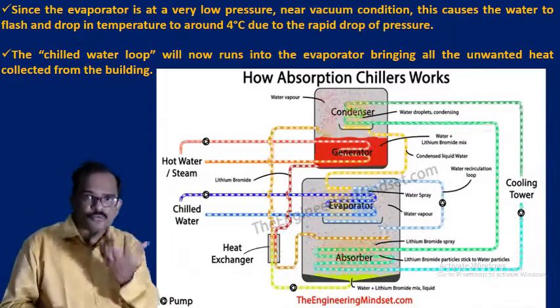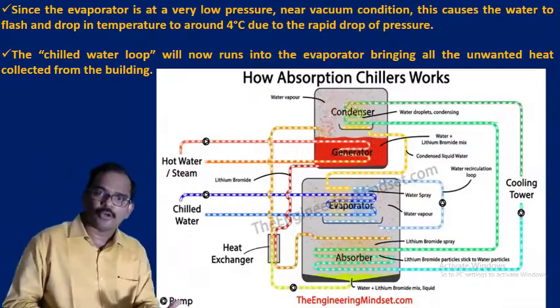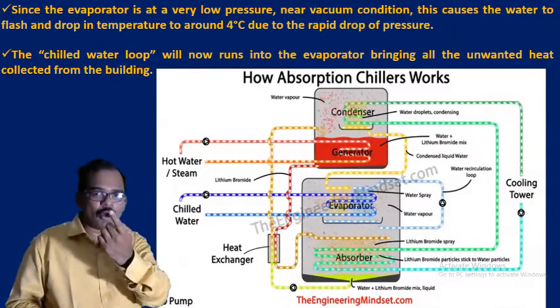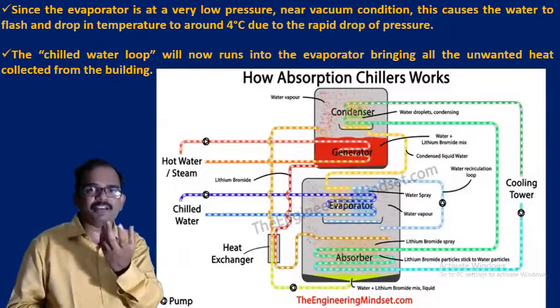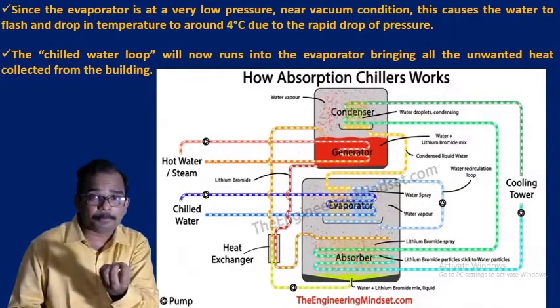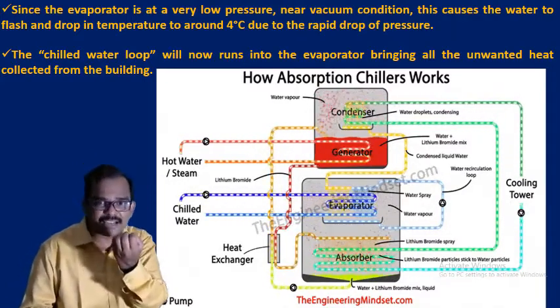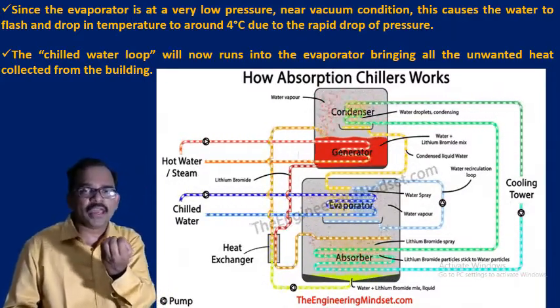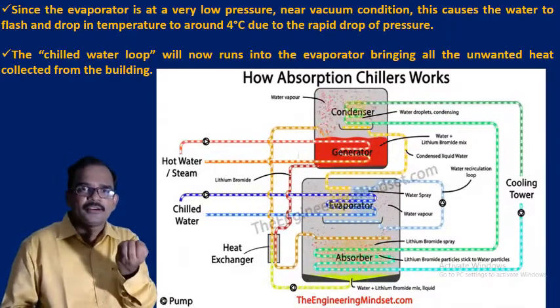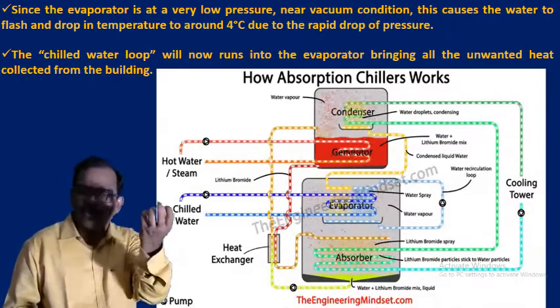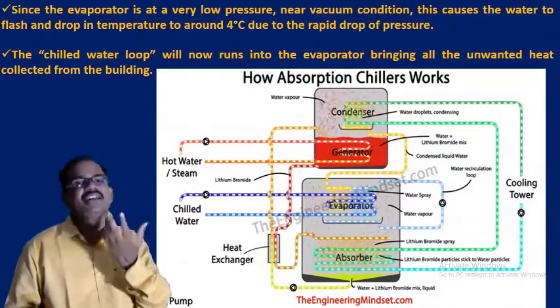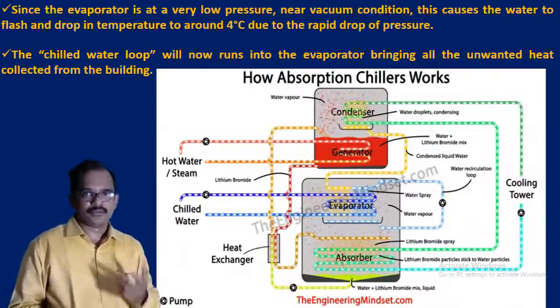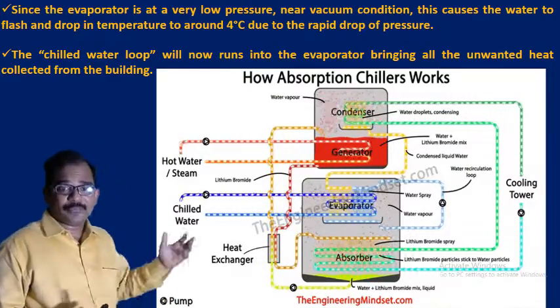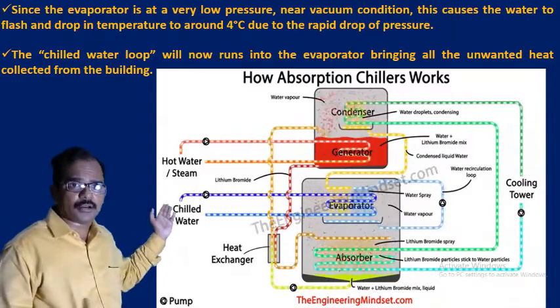As the pressure reduces, the boiling point of water also will reduce, because the evaporator and absorber will be kept under vacuum condition at a low pressure of 0.0084 atmospheres. The boiling point of water at this pressure will be only 4 degrees centigrade. Right. And there is one more loop called the chilled water loop.